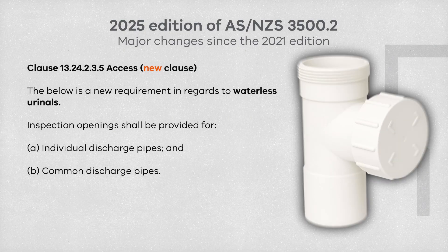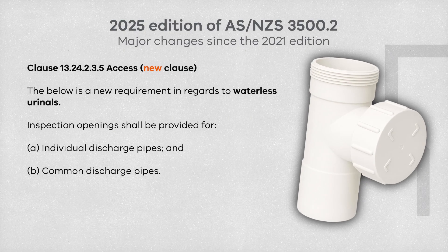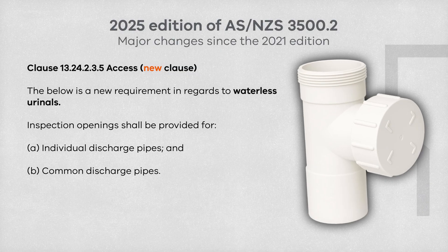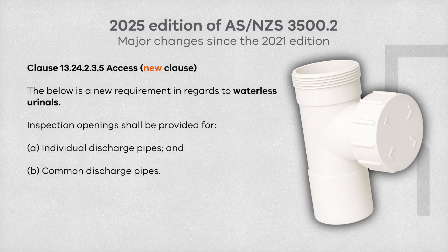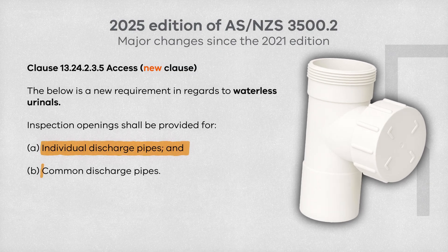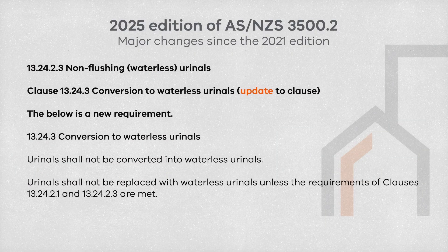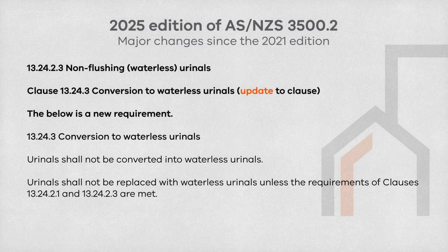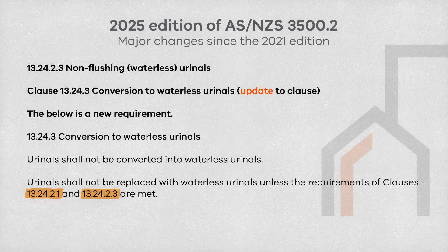A new clause has been introduced to outline the requirements for inspection openings on waterless urinals, including provisions for both individual and common discharge pipes. The clause regarding conversion to waterless urinals now has an update. It now clearly states that urinals must not be converted to waterless urinals, nor replaced with waterless urinals, unless the requirements of clauses 13.24.2.1 and 13.24.2.3 have both been met.